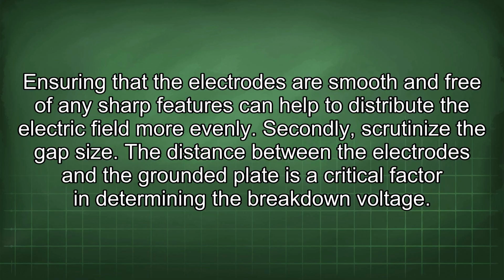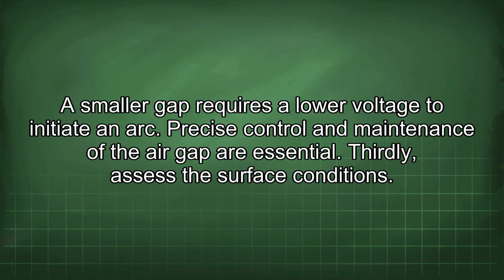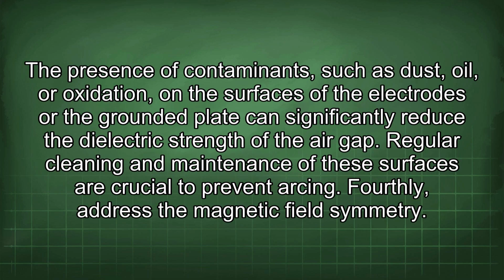The distance between the electrodes and the grounded plate is a critical factor in determining the breakdown voltage. A smaller gap requires a lower voltage to initiate an arc. Precise control and maintenance of the air gap are essential. Thirdly, assess the surface conditions. The presence of contaminants such as dust, oil, or oxidation on the surfaces of the electrodes or the grounded plate can significantly reduce the dielectric strength of the air gap. Regular cleaning and maintenance of these surfaces are crucial to prevent arcing.